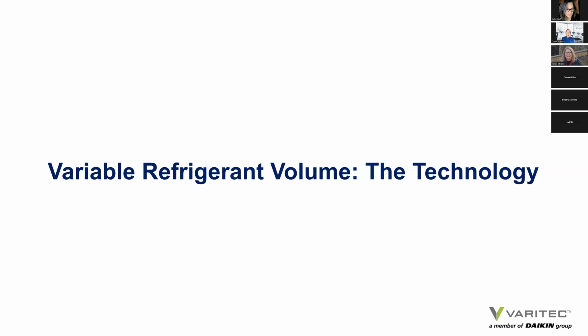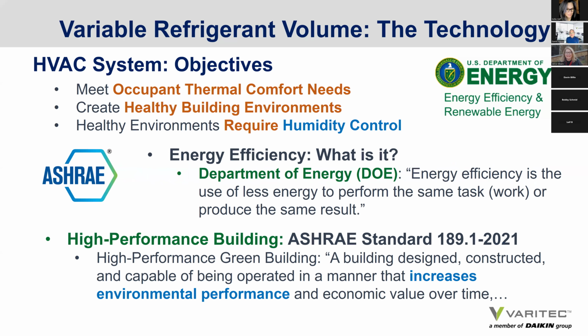So, with that said, what is variable refrigerant volume technology? What is the technology and what is its inherent efficiency advantage? First of all, let's review why we need HVAC systems to begin with. First and foremost, it's to maintain occupant thermal comfort. And we're becoming more aware, over the last 20, 30, 40 years since the sick building syndrome of the 1970s, that the mechanical system, the HVAC system, can actually contribute to healthier building environments. And one of the things that we need to do to do that is to maintain and regulate humidity control.